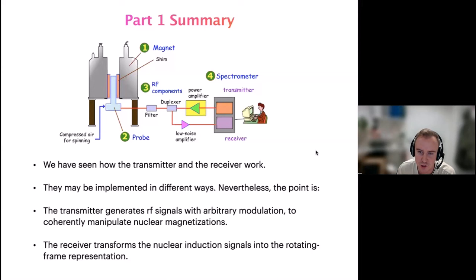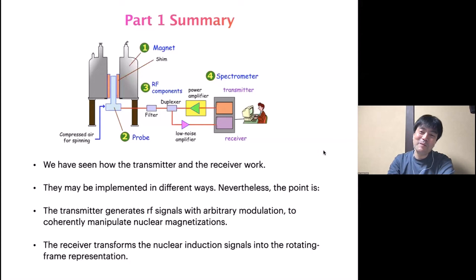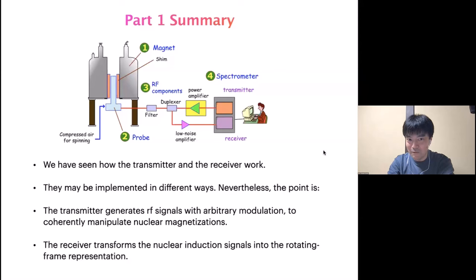From Walt Mussewski: commercial spectrometers have extensive RF shielding, but your spectrometer board is mounted on the wall — is RF shielding less important than we think? Maybe. It depends on the environment. If you're not lucky, you may be working in a very noisy environment, in which case you may want to shield the system. But in some environments — for example, an MRI room in a hospital — I found the environment so silent that you don't have to shield the system at all.